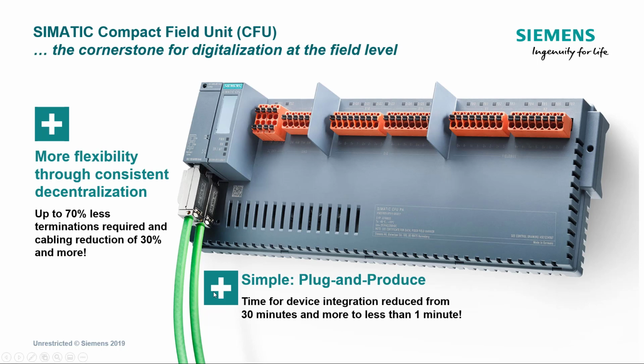So this one here, time to device integration. It doesn't sound much, but if you're having to integrate a device and find the GSD, I mean 30 minutes is optimistic. It's probably going to take longer than that if you don't know where to find the GSD from. We've all been there. But if you've got 50 devices, this time can start to stack up. If you're using the plug and produce, 1 minute to get that device transmitting its data to the DCS or the PLC. Now the other thing we haven't looked at, of course, because this is Profinet, it's a lot quicker than Profibus DP to PA.